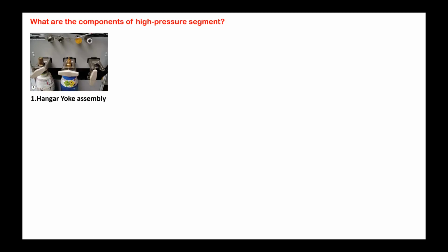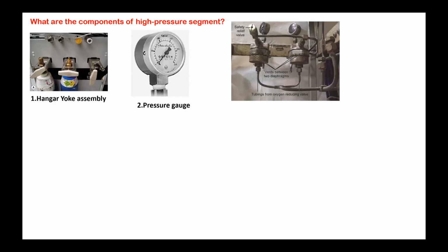What are the components of the high pressure segment? You know, the anesthesia machine system is divided into high pressure, intermediate pressure, and low pressure systems. So what are the components in the high pressure segment? From the pipeline, cylinder, hanger yoke assembly, pressure gauge, and pressure regulators.